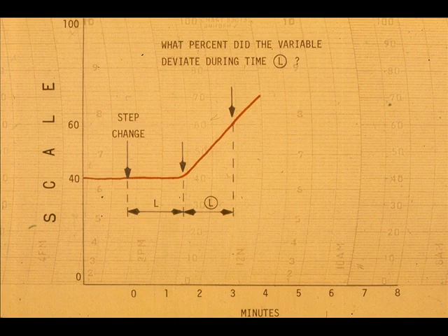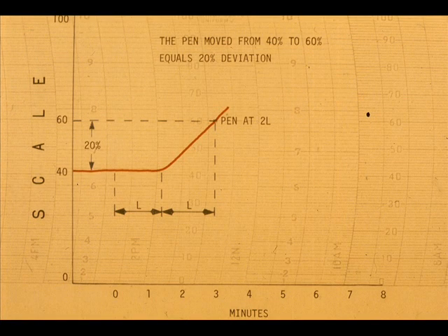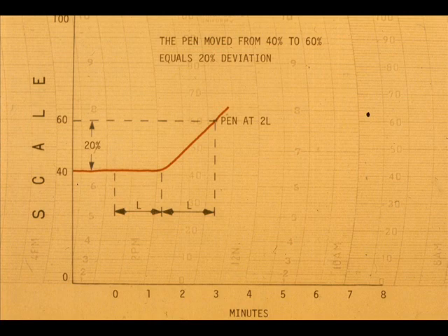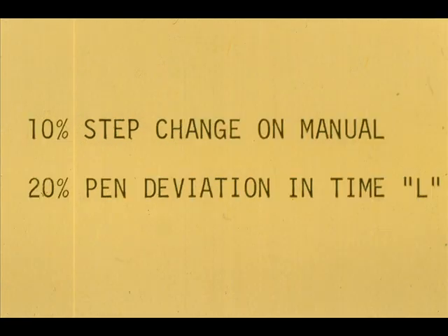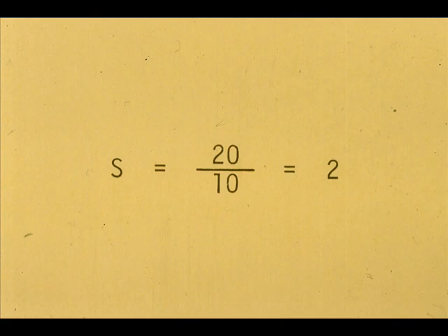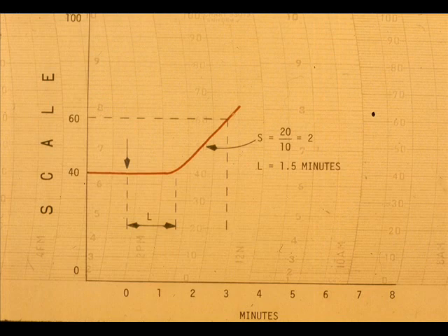Now, measure the percent of full scale the process deviated during the second time period equal to L. By projecting the slope of the curve in the time for the second L back to the scale, we get a deviation of 20% scale. We are interested in percent of deviation divided by percent of step change to get the slope S. We made a 10% output step change originally, and our deviation in time L was 20%, so S equals 20 divided by 10, which equals 2. We know S and we know time L — this is all the information we need to calculate the optimum response adjustments.